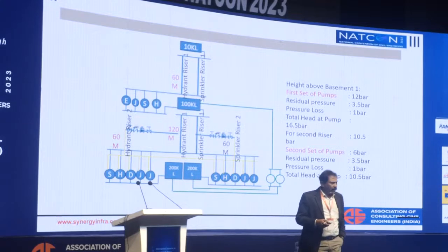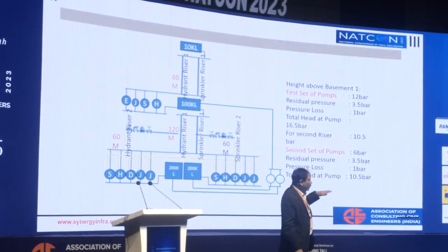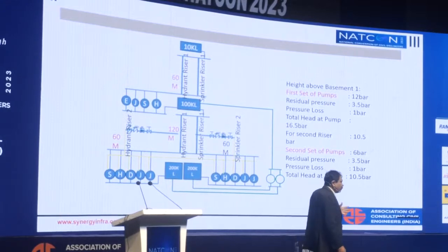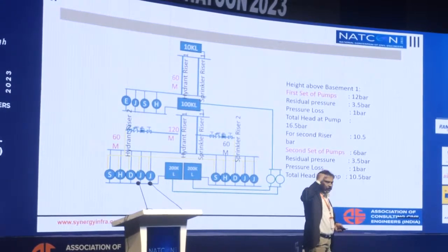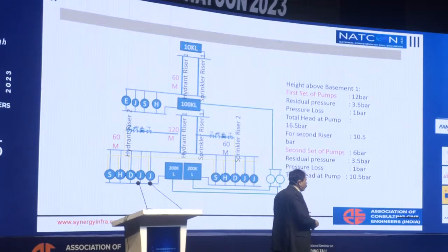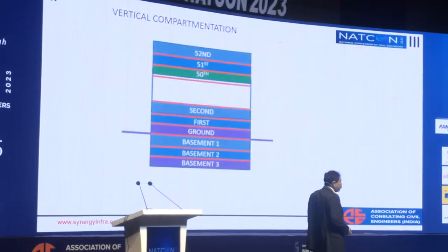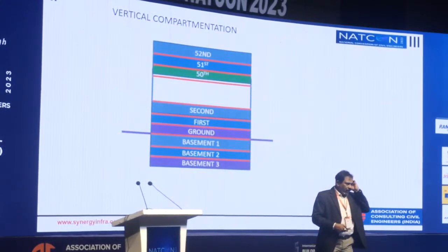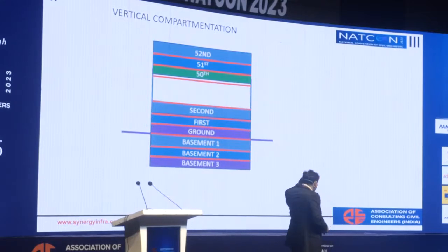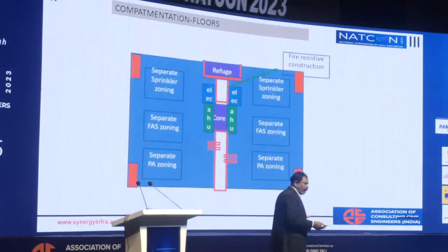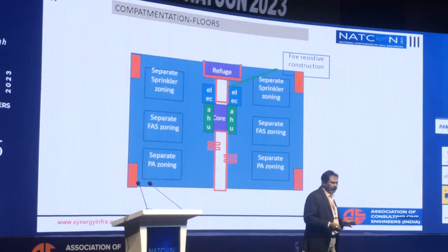Otherwise, they were going by the code itself. For one of the buildings of 155 meters, they provided fire pumps at the terrace. It doesn't make sense. This is supposed to take care of the floors above that level. That is the reason we brought it down to the middle level. Some of the other codes, like the Middle East ones, say around 90 meters you need to have separate systems. And the most important thing is you have to look at every building compartmented vertically as well as horizontally. If you have horizontal and vertical compartmentation, and all services, whether sprinklers or electrical or air conditioning systems, are separately designed for every compartment, then there will not be any major issues.